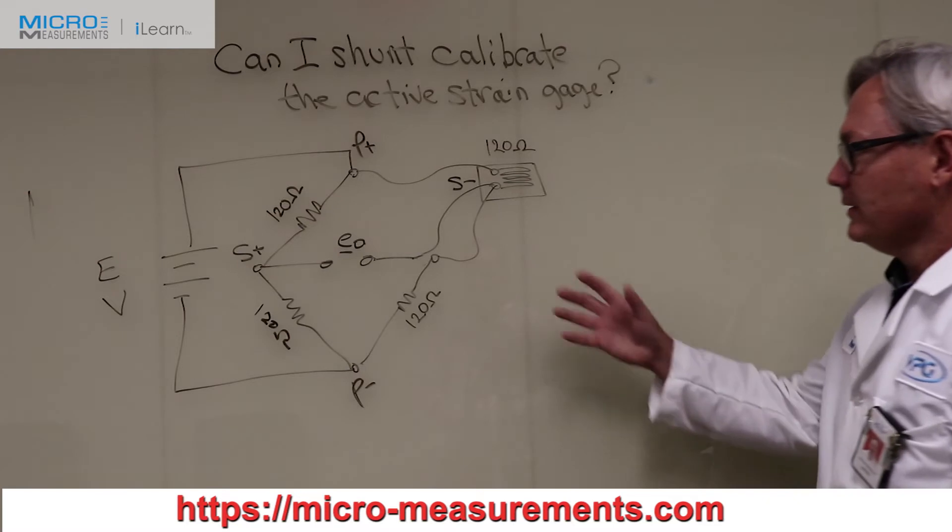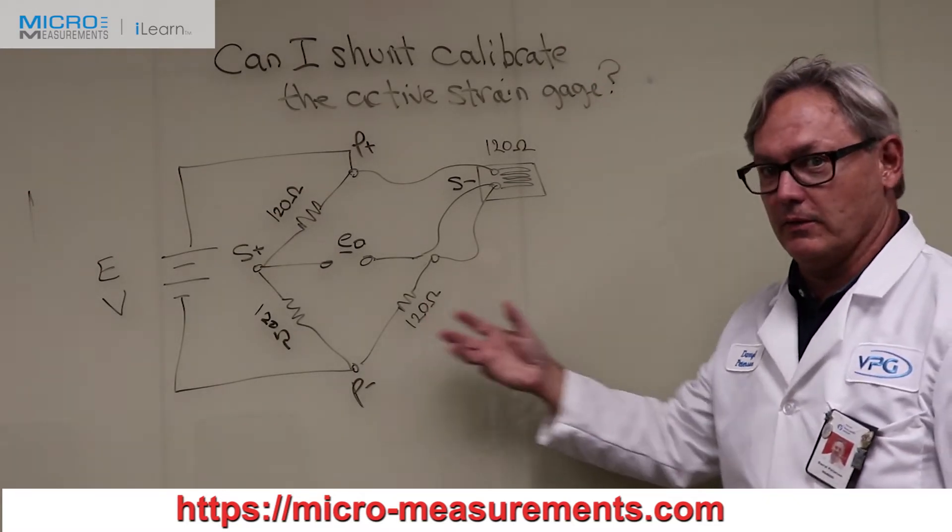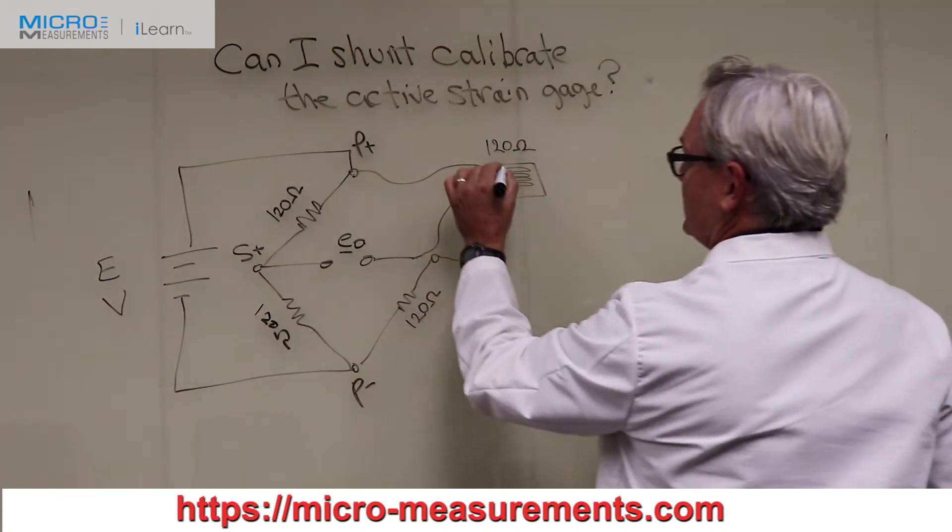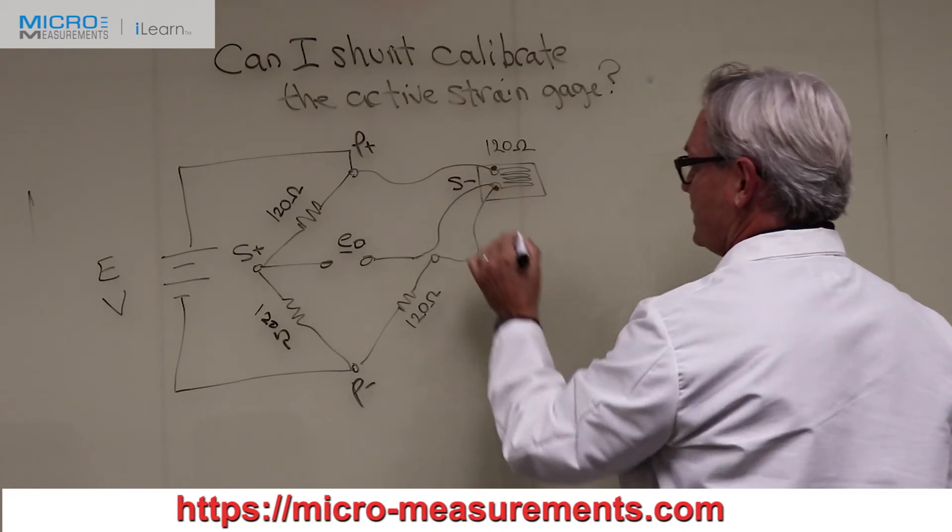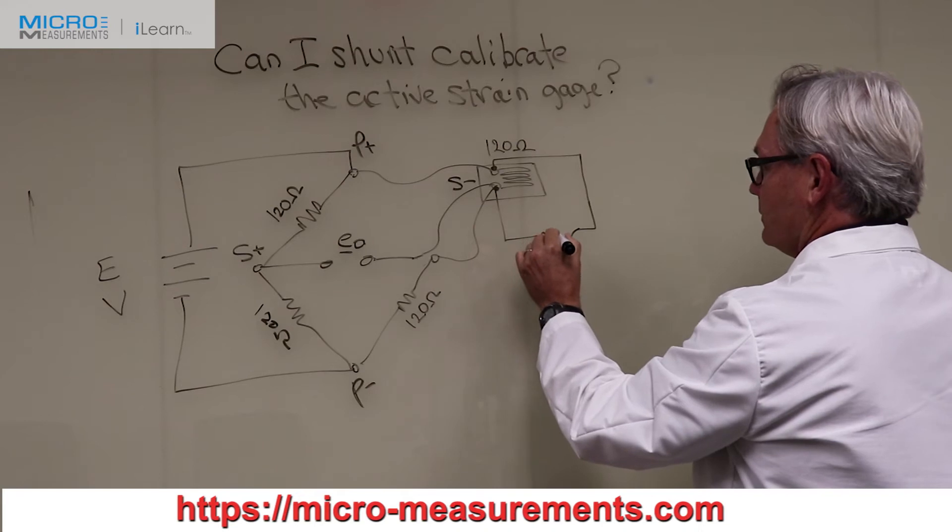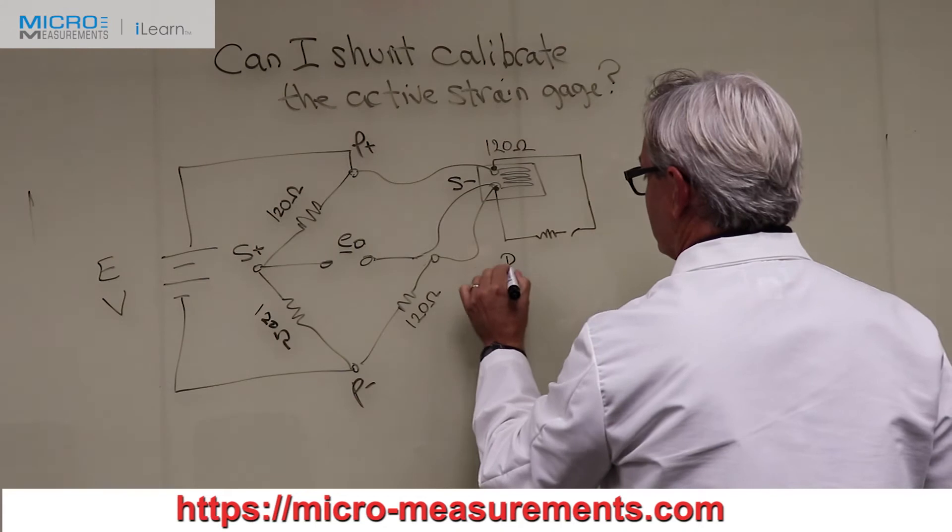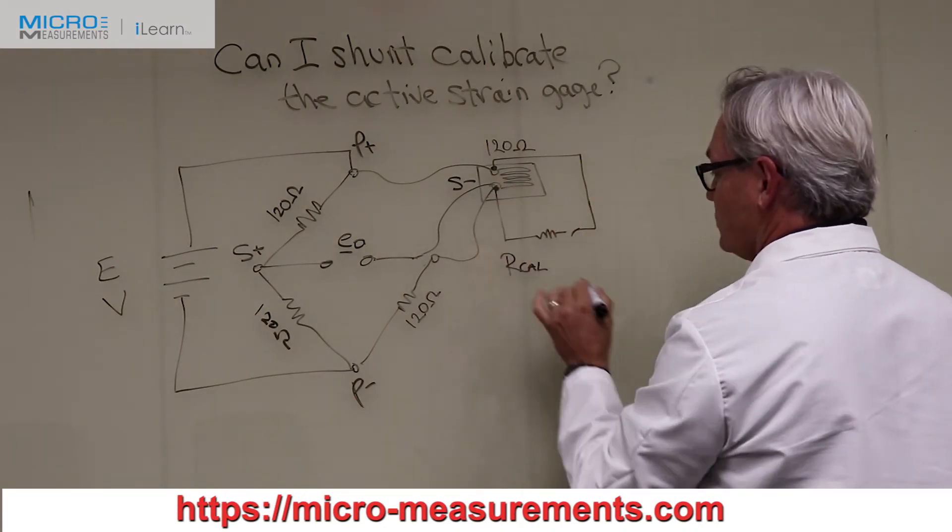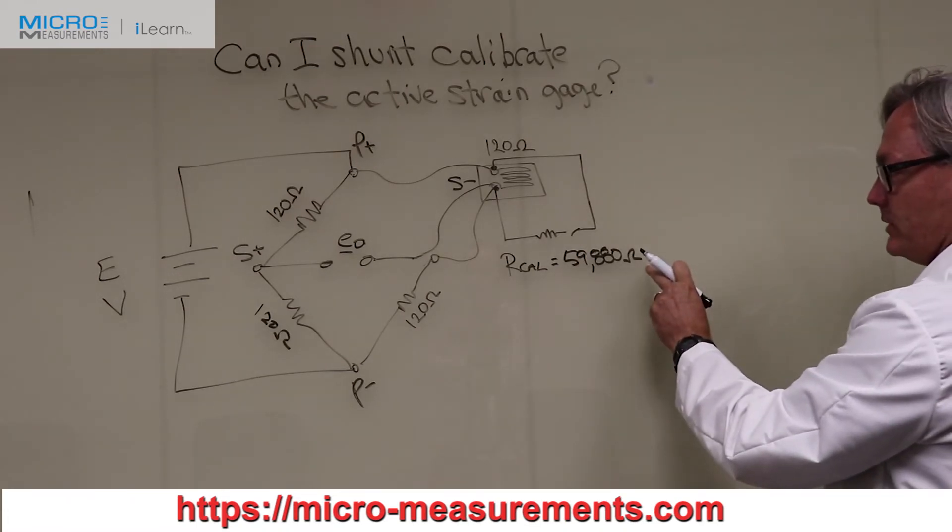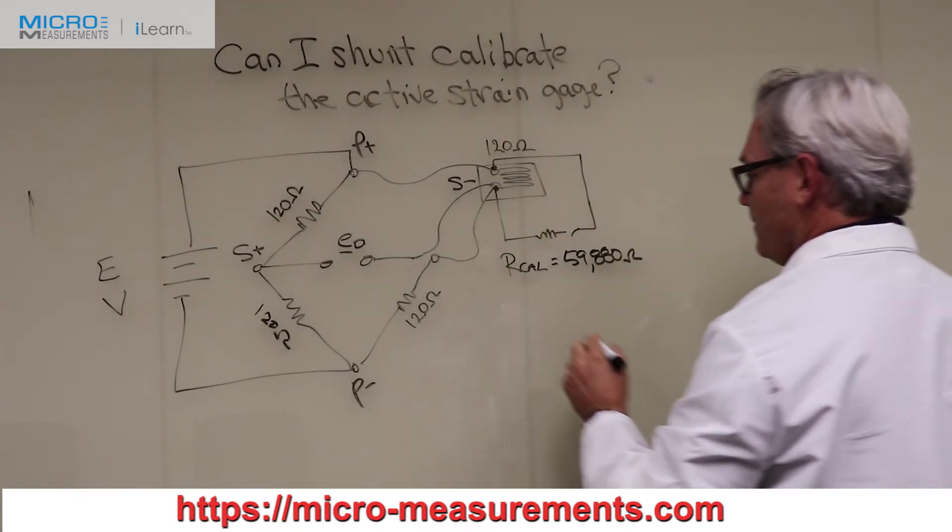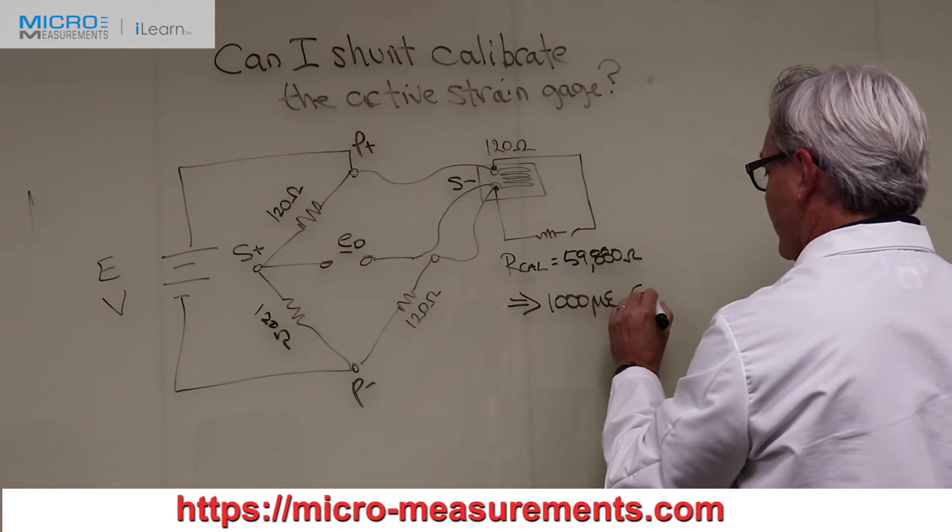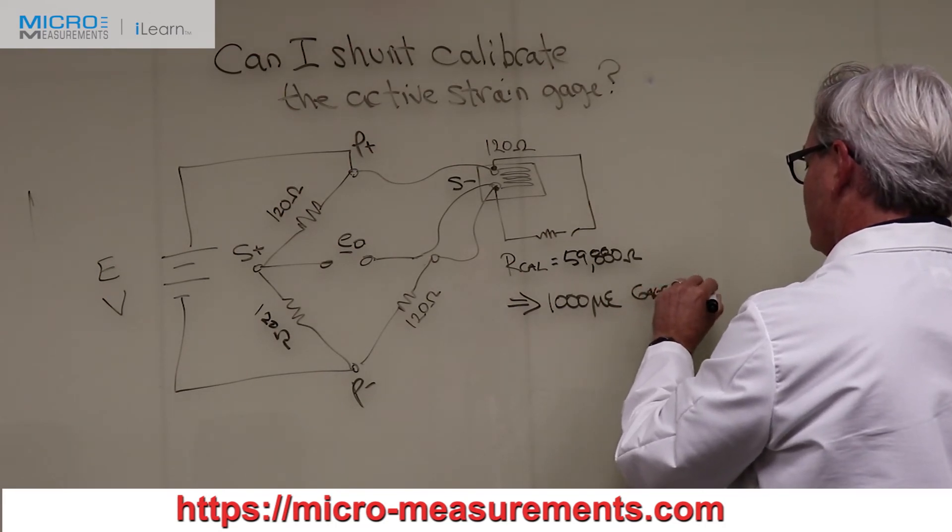Now, shunt calibration is a method that we use in order to scale this circuit. And a common question we get is, can I shunt calibrate the active strain gauge? And what that would mean is that we would have to take a resistor and connect it here across the tabs of the strain gauge. Typically, you would put a switch in that loop along with the resistor. And if I happen to pick this resistor, let's call this resistor R-CAL. And oftentimes, for a 120 ohm strain gauge, we would pick a resistor that's 59,880 ohms. The reason we picked this resistor is that if you take it and you shunt calibrate it across the 120 ohm strain gauge, that produces a simulated microstrain of 1,000. And that's based on a gauge factor equal to 2.